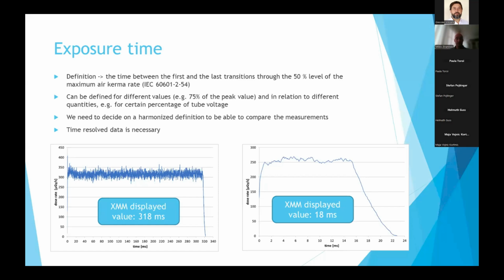For example, if you use a different level, a 75% level, or if you look at tube voltage instead of air kerma rate. So we need to make sure that everybody is using the same definition before we can standardize this quantity, before we can provide really harmonized, standardized calibrations, and before we can compare the measurements. And here in these graphs, you can see, for example, that on the second graph, exposure time is actually 18 milliseconds, because this whole part of the exposure, when the dose rate is rapidly decreasing, is excluded from the calculation. So we need time resolved data to be able to determine exposure time.